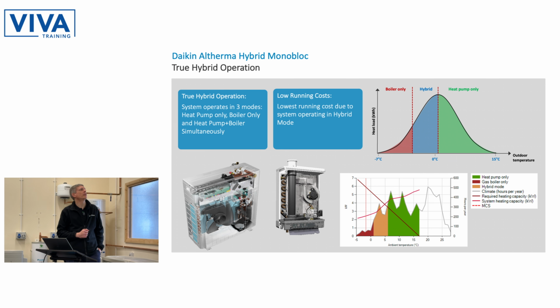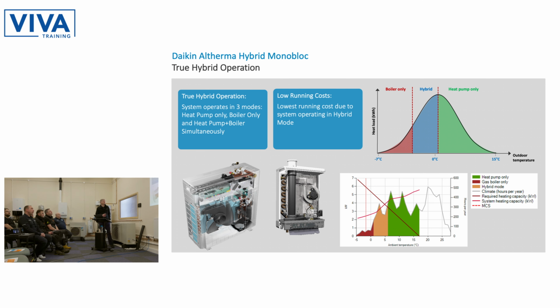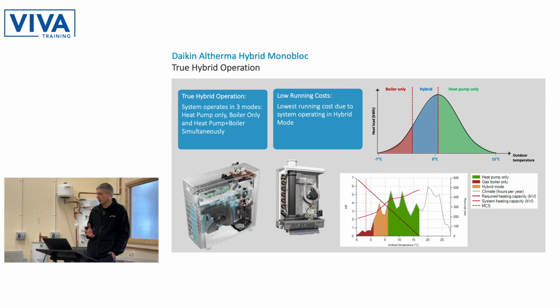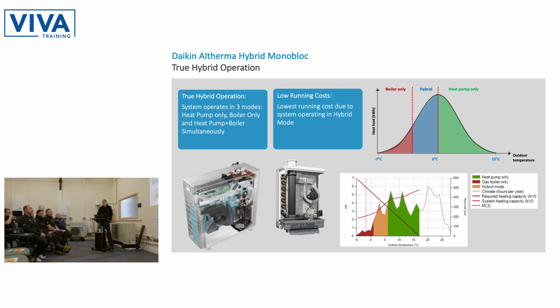So as I mentioned, the hybrid system can operate in three modes. We've got heat pump only, boiler only, or both operating together, and we're calling this true hybrid operation. For some of our competitors, as I mentioned, you can only have the heat pump or the boiler. Here we get both, and that significantly helps with the running costs. So if we look at a year, perhaps the heating season, -7 to +15, the biggest chunk of the heating demand over the course of a year, we're expecting that to be the heat pump only, followed by both operating together, and then when it's really cold, boiler only operation, when the heat pump can't deliver the performance required.